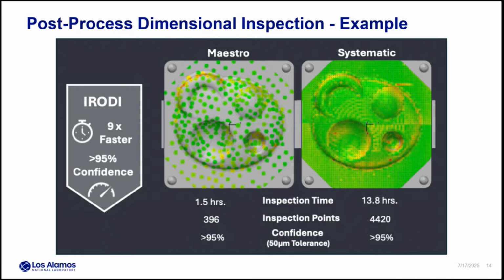The output from that exercise that they went through is captured in this image here, and there's a lot of valuable takeaways from this. First off, you have a systematic inspection shown on the right side. That's a very discrete set of points that have been taken. It's been programmed in the CMM. It's gone off and touched that surface in a number of regular points, and it's done a very good job of capturing the geometry of that complex contour of that NIST part.